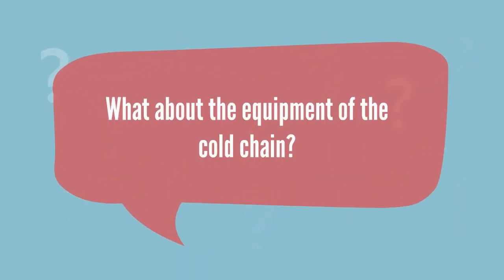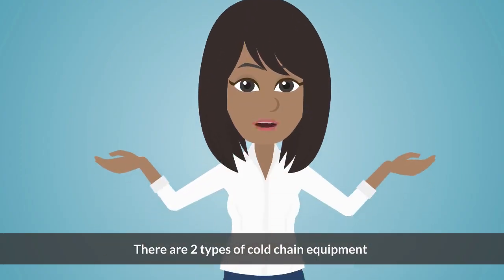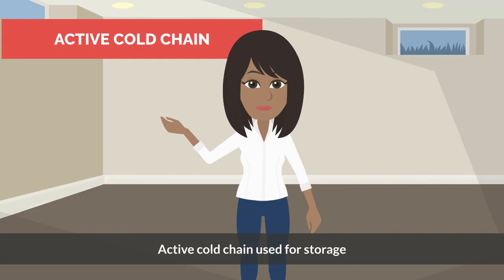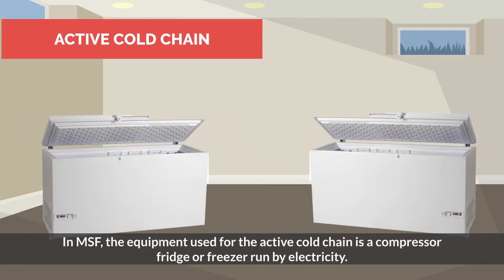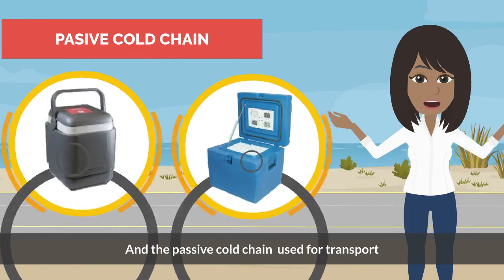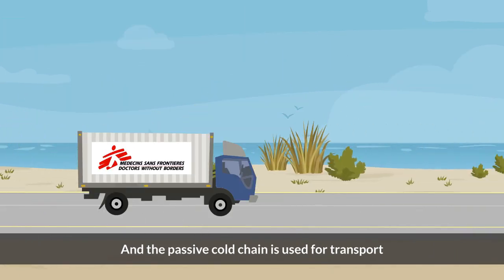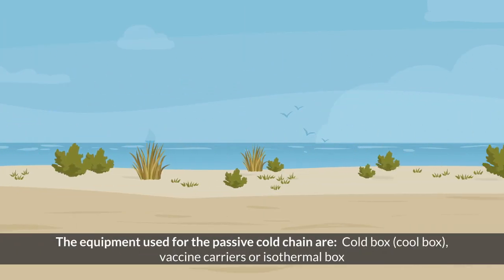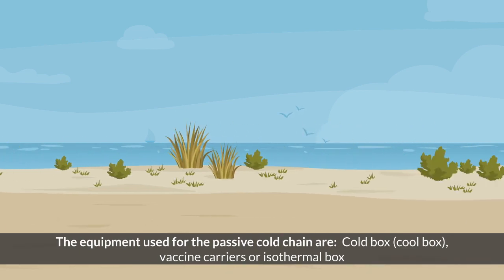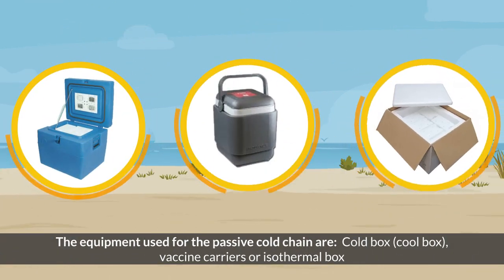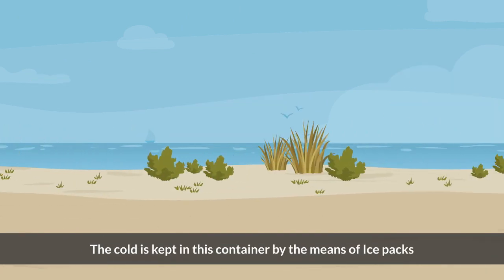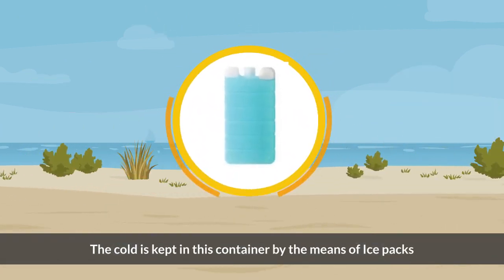What about the equipment of the cold chain? There are two types of cold chain equipment. Active cold chain, used for storage — in MSF, the equipment used for the active cold chain is a compressor fridge or freezer run by electricity. And the passive cold chain, used for transport — the equipment includes cold boxes, cool boxes, vaccine carriers, or isothermal boxes. The cold is kept in these containers by means of ice packs.